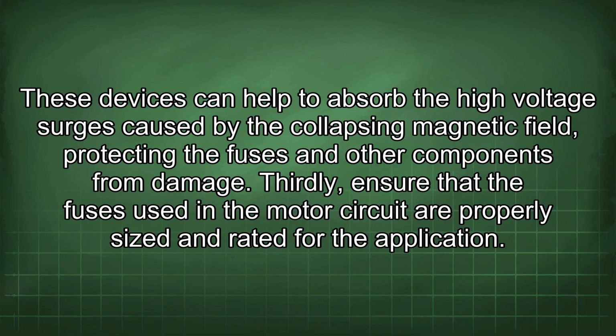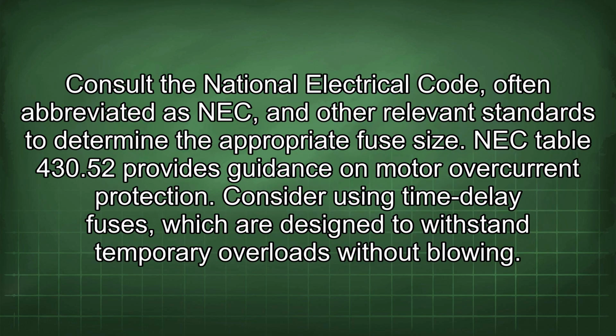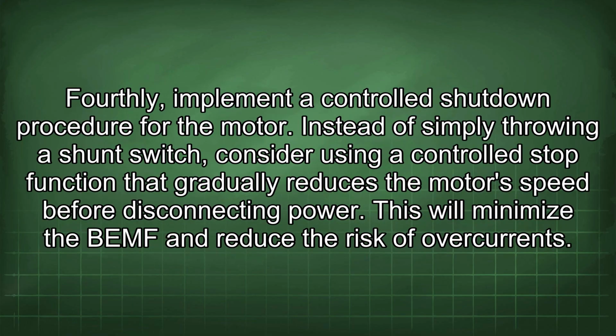other components from damage. Thirdly, ensure that the fuses used in the motor circuit are properly sized and rated for the application. Consult the National Electrical Code, often abbreviated as NEC, and other relevant standards to determine the appropriate fuse size. NEC Table 430.52 provides guidance on motor overcurrent protection. Consider using time delay fuses, which are designed to withstand temporary overloads without blowing. Fourthly, implement a controlled shutdown procedure for the motor. Instead of simply throwing a shunt switch, consider using a controlled stop function that gradually reduces the motor's speed before disconnecting power. This will minimize the BEMF and reduce the risk of overcurrents.